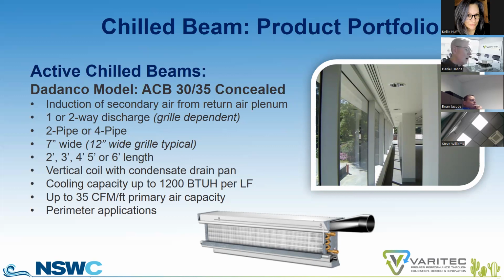And working with PAE engineers out of Oregon and the architectural group Architecton, they embraced an entirely unique design solution for active chill beams that gave me pause when I was challenged with it. And they were, Dan, what if we turned a chill beam into a condensing device, providing we had a chill beam with a drain pan, so we could actually collect condensate during monsoon. And we effectively did that at Architecton's award-winning Helios project. All the chill beams are condensing devices in that building, and yet the energy profile and savings, because of the limited time of year we're in monsoon, made all the sense in the world.